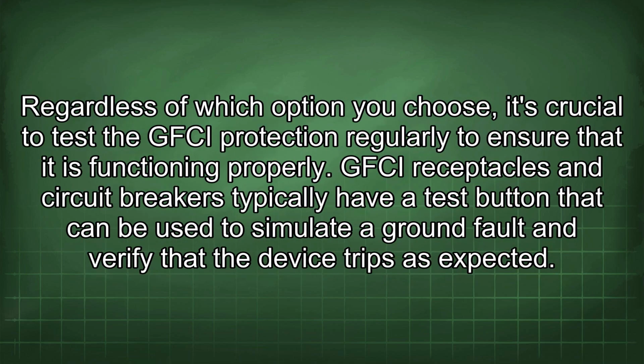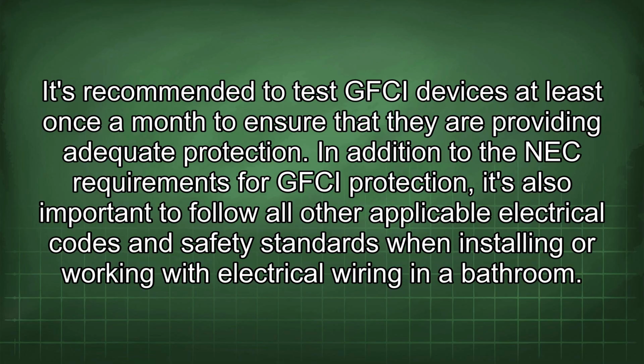fault. Regardless of which option you choose, it's crucial to test the GFCI protection regularly to ensure that it is functioning properly. GFCI receptacles and circuit breakers typically have a test button that can be used to simulate a ground fault and verify that the device trips as expected. It's recommended to test GFCI devices at least once a month to ensure that they are providing adequate protection.